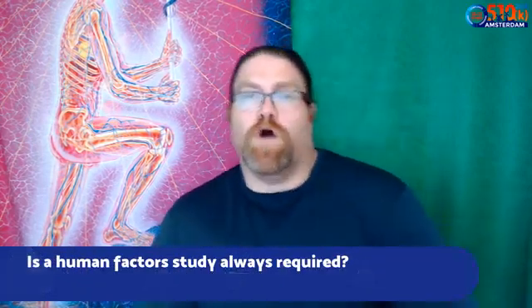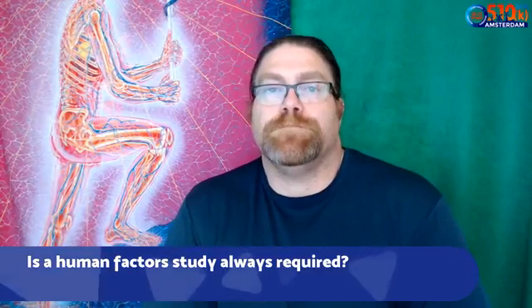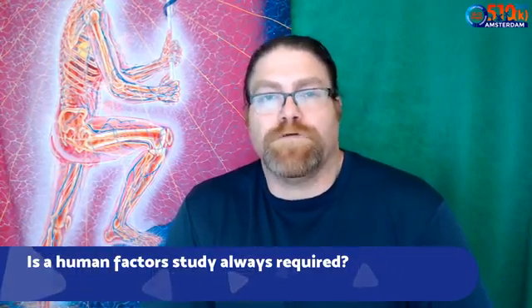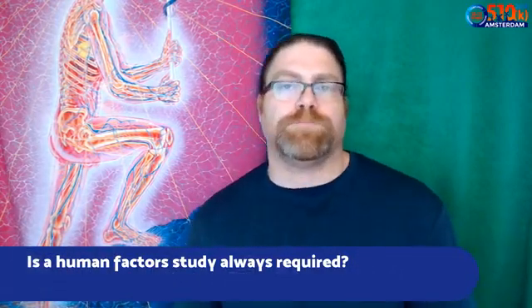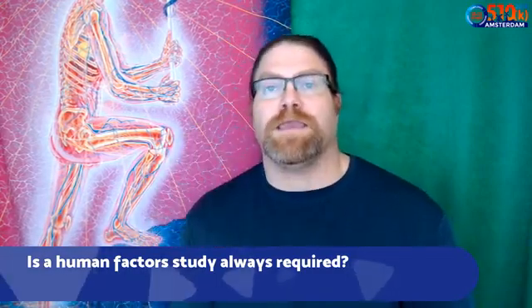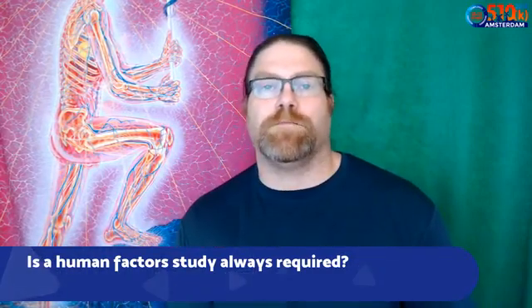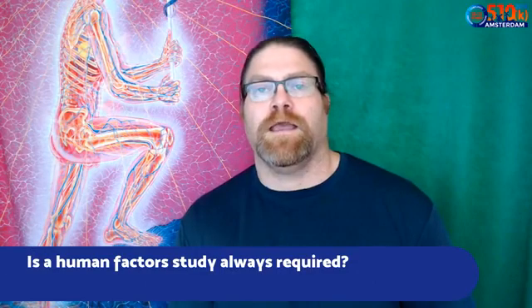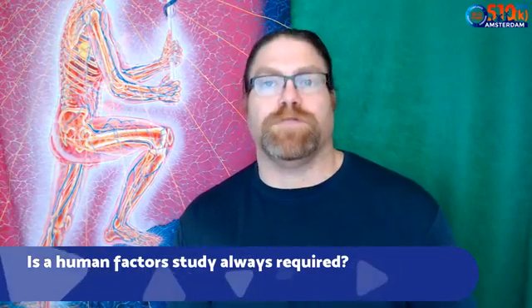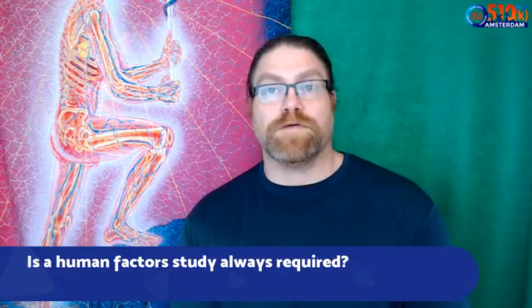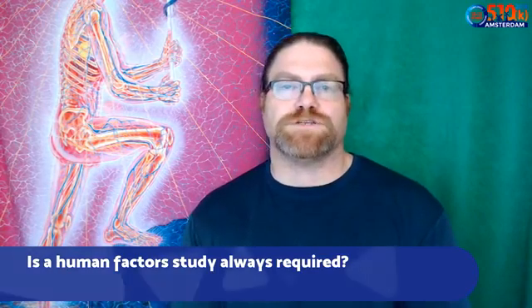Is a human factors study always required? No, it's not always required. If you make a product, the whole premise behind a 510K submission is that there's another product already legally marketed in the U.S. market that is similar to yours, equivalent. So the more equivalent it is, the less likely you have to do a human factors study.